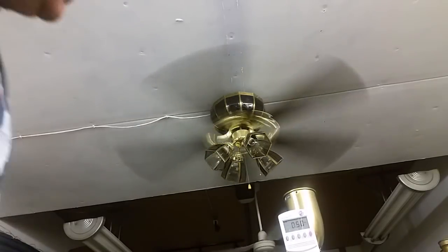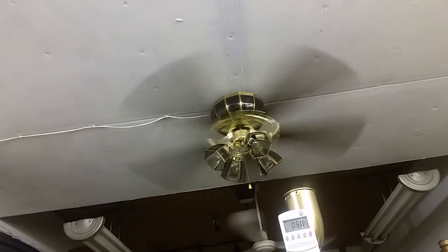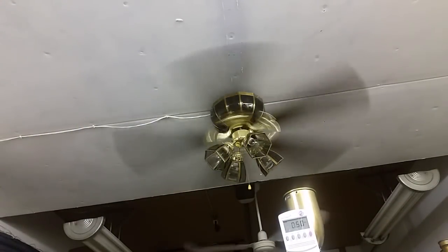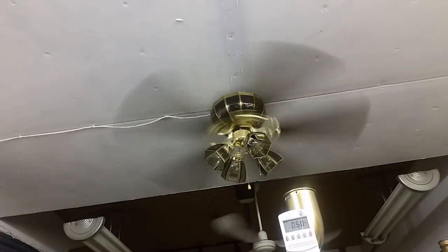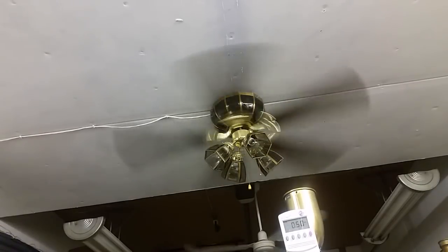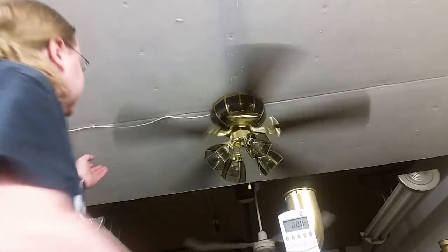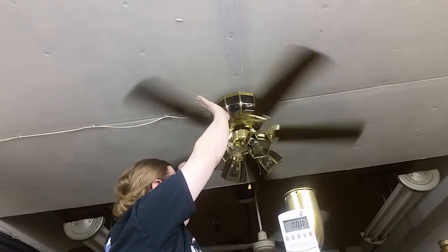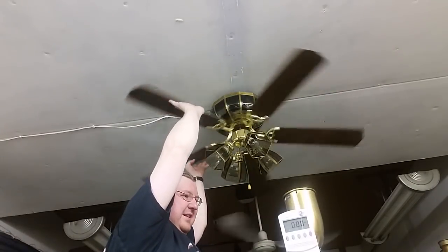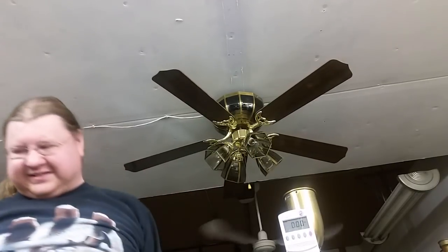And also solid state. Well, here's solid state high. Pretty much the same current draw, though. Yeah. Not much different, barely. But that Pro Line 2 is quiet on a solid state. So a fan like that, or that new fan that you gave me, I had to do the same. Okay, because, yeah, no 4-speed will work on it, but a solid state will. Same with the cast motor Daytons, they work nicely.